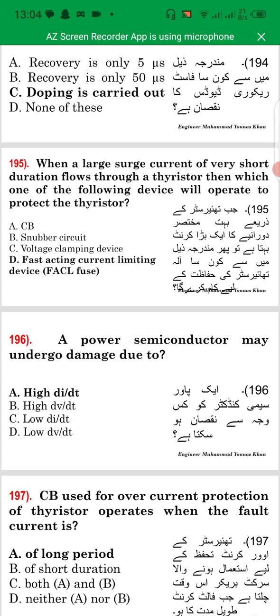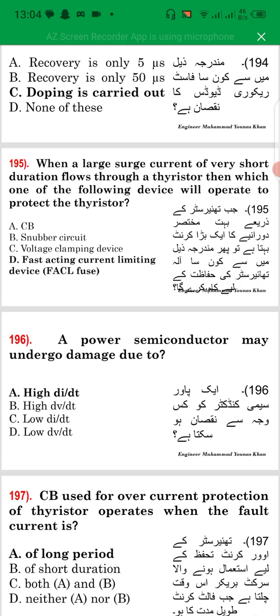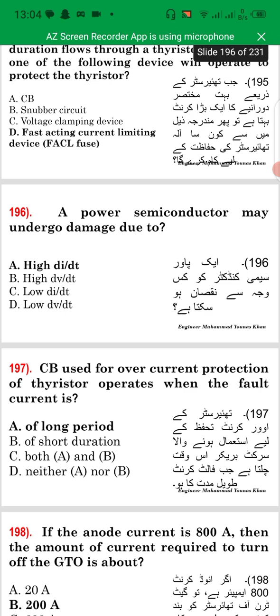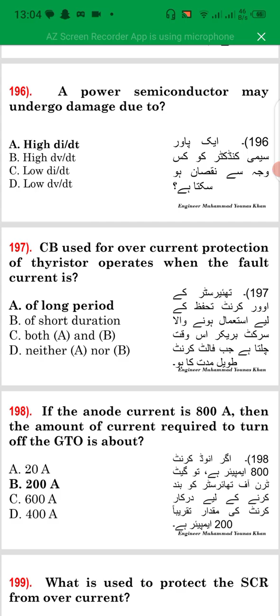Doping is carried out. When a large surge current of very short duration flows through a thyristor, which of the following devices will operate to protect the thyristor? Fast acting current limiting device. Fuse. A power semiconductor may undergo damage due to high di by dt. CB used for overcurrent protection of thyristors operates when the fault current is of long period.